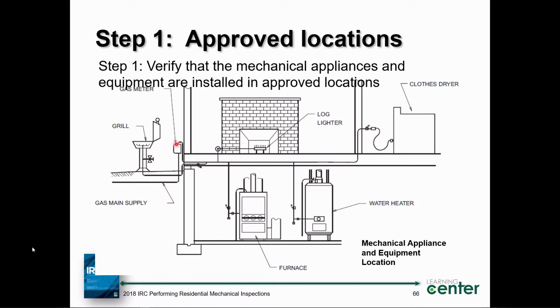From that point, all the design, the installation, and all the code requirements come from this point all the way through the gas piping system, including the fuel gas appliance connectors. What am I talking about? We take care of all the fittings, the piping, the installation of the piping, the sizing of the piping, all the way through to and including all valves, all regulators, and the appliance connectors that connect the appliance to the gas piping system.